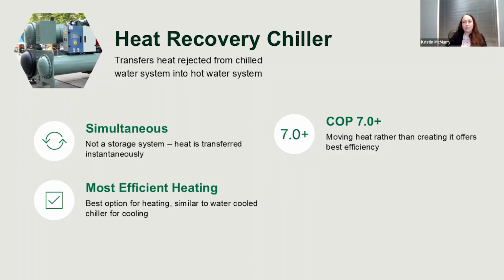So we've gone from less than 1 all the way up to 7 with this technology. But there are some caveats - it only works with simultaneous heating and cooling. You do need to have heating and cooling loads at the same time. It's not a storage system, but it is the most efficient of the ones we're going to talk about.